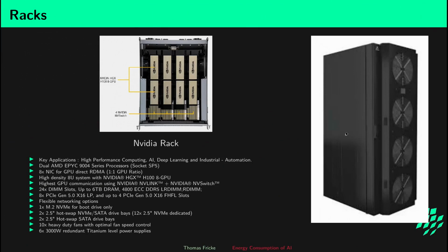Now we stack this entire thing into racks. A typical data center has standardized racks, but with this new type of NVIDIA GPUs, we have a different kind of rack: 700 watts times 8, and typically 3 of these units, so you need 6 times 3,000 watts to produce the energy consumed by the NVIDIA graphic cards. So effectively you need more or less 30 kilowatts.